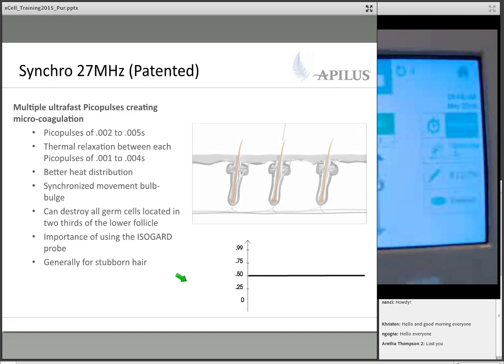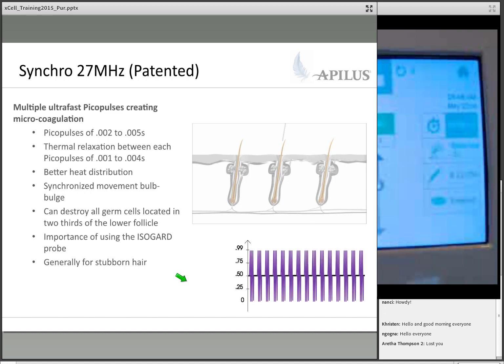So Synchro. Synchro was first put out on the platinum machines and definitely refined a little bit more on the xCell. So there is a lot that you can do with Synchro on the xCell machines. Essentially what Synchro is, I know that when you look at the machine, you see 1 time and 1 intensity, but Synchro is actually a lot of very, very quick pulses of Picoflash, one after the other, with a short little relaxation time in between. So I like this graph because again, you can sort of see what this looks like. And let's say this is a ½ a second pulse in totality. You have a lot of very, very short pulses of Picoflash with a little bit of thermal relaxation time in between. That's the time in between my pulses.